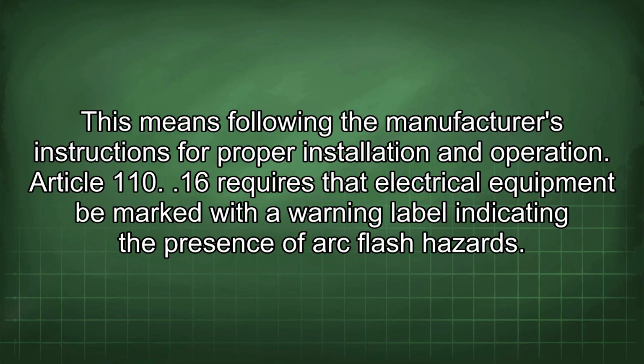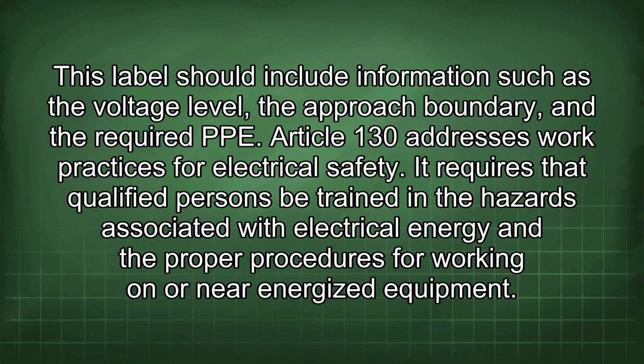110.16 requires that electrical equipment be marked with a warning label indicating the presence of arc flash hazards. This label should include information such as the voltage level, the approach boundary, and the required PPE. Article 130 addresses work practices for electrical safety. It requires that qualified persons be trained in the hazards associated with electrical energy and the proper procedures for working on or near energized equipment.